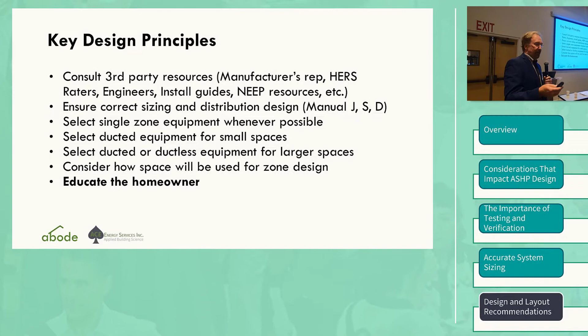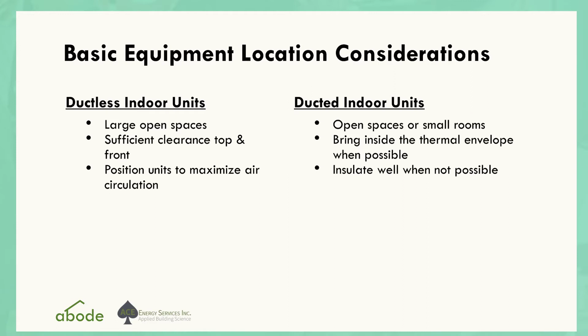Basic equipment locations and considerations: ductless units can be used in large open spaces, but you need sufficient clearances top and bottom, and you want to position the air units to maximize circulation - I'll show some examples. Ducted indoor units are good for small rooms and open spaces. You want to put the ducted system inside conditioned space where possible, and insulate well. If you've got a ducted system in a cold attic, insulate it as best you can.